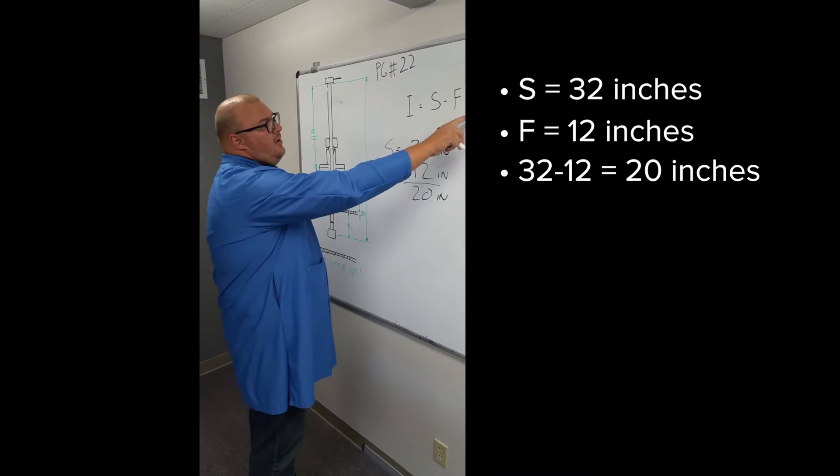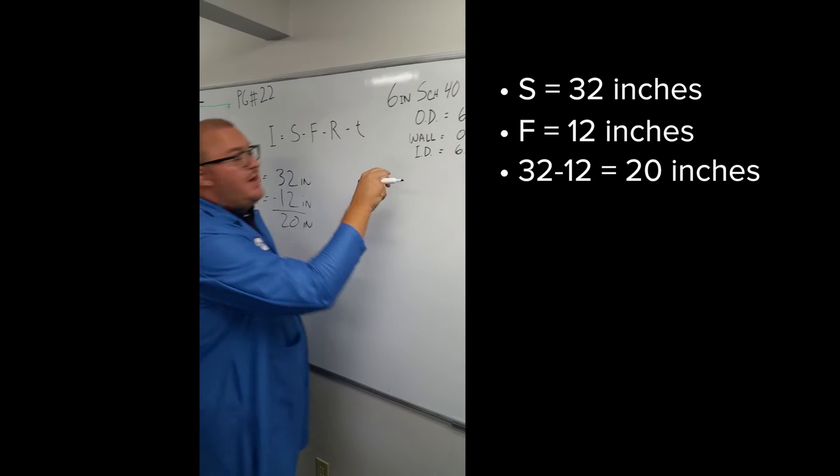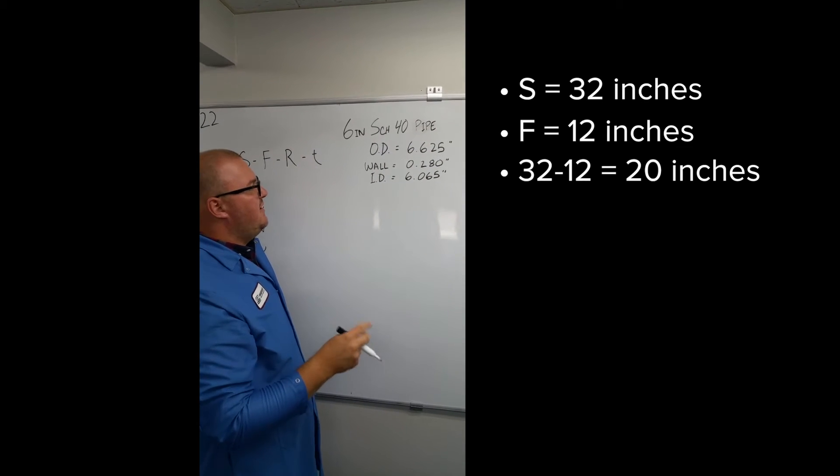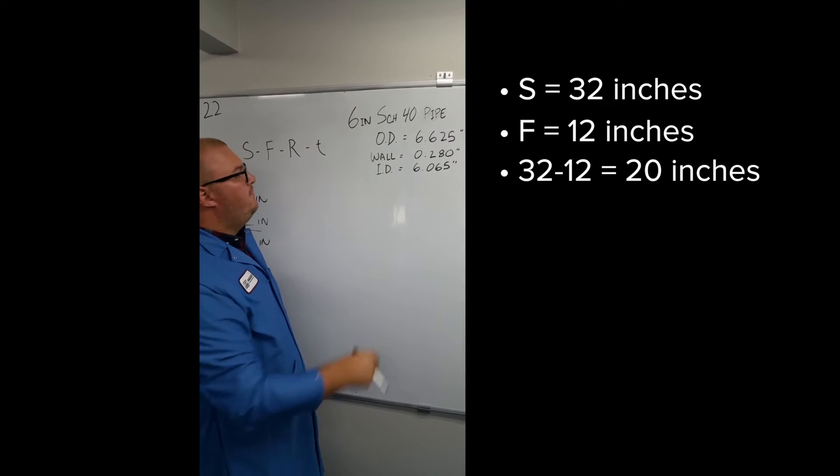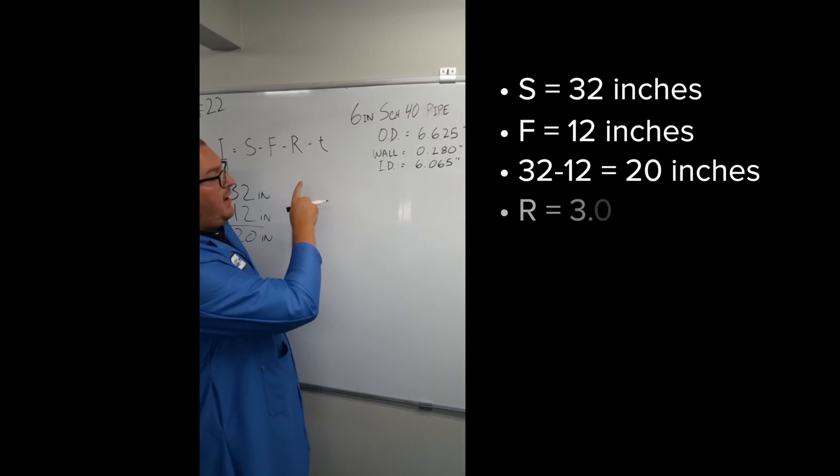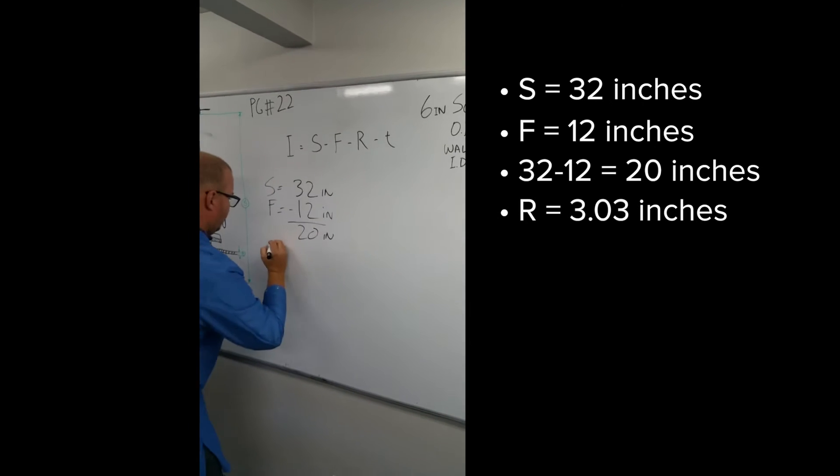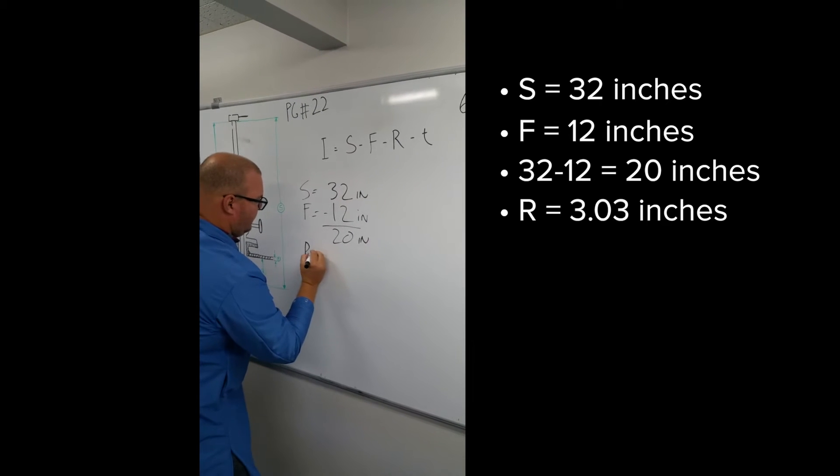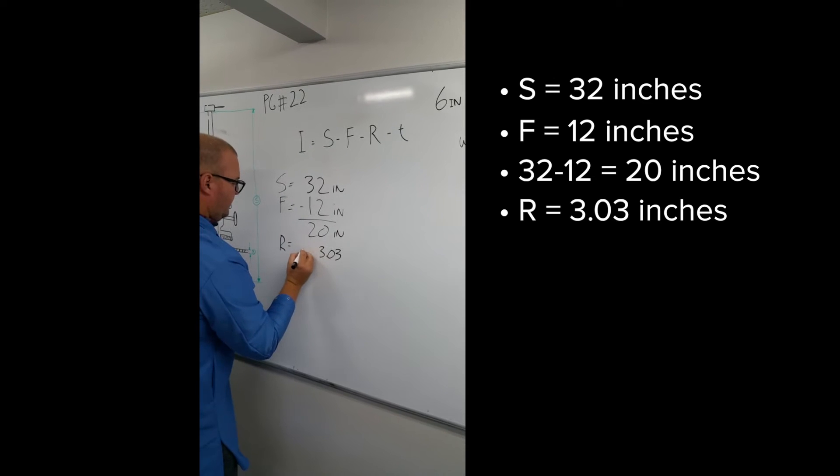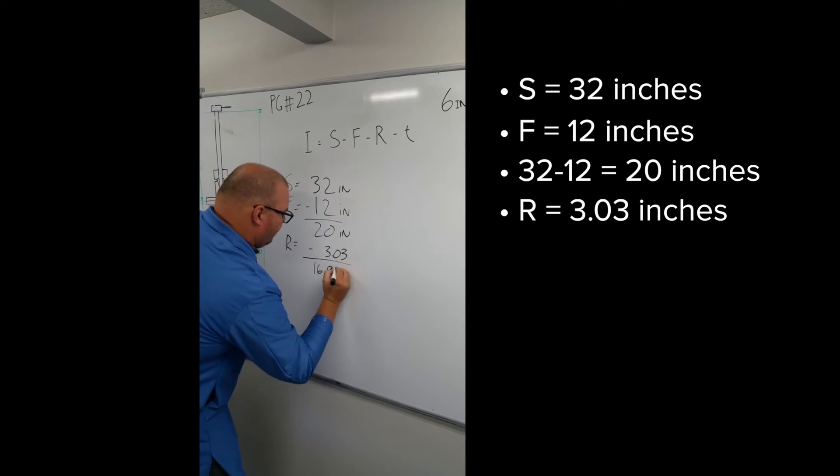Next is R which is the radius of the pipe. Over here I have some information about our pipe downstairs. 6 inch schedule 40 pipe. I just took this off a standard pipe schedule table. The OD, the wall thickness, and the ID. R is the radius of the pipe. All we need to do is take the ID and divide it by 2. Our radius is equal to 3.03 inches. Subtract that and we get 16.97 inches.